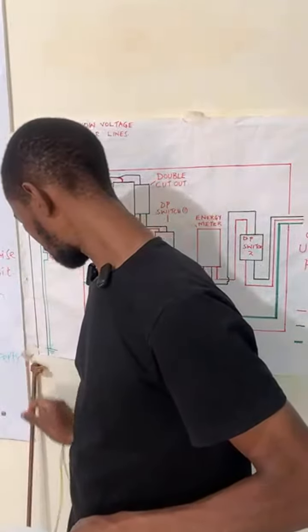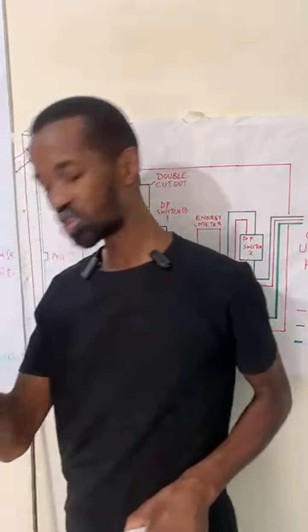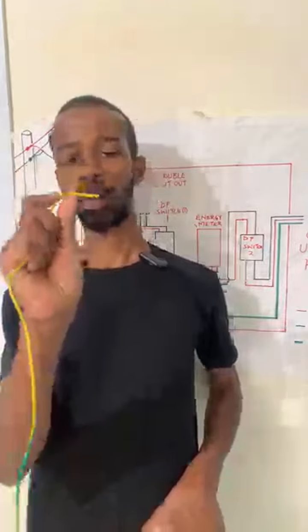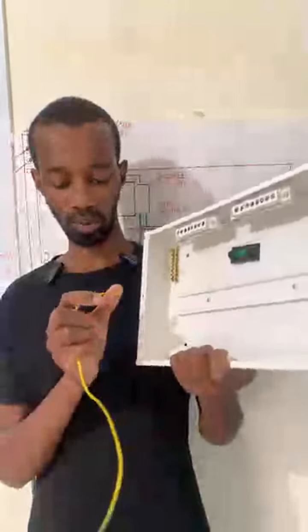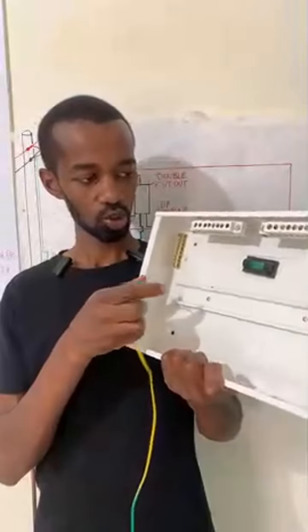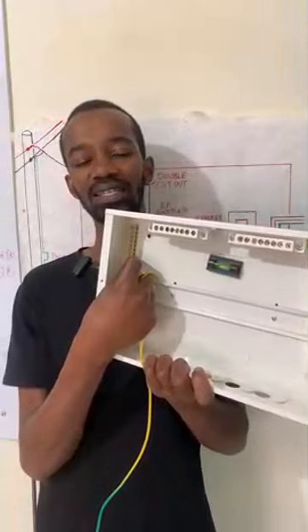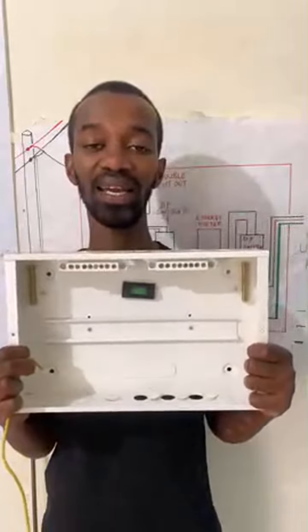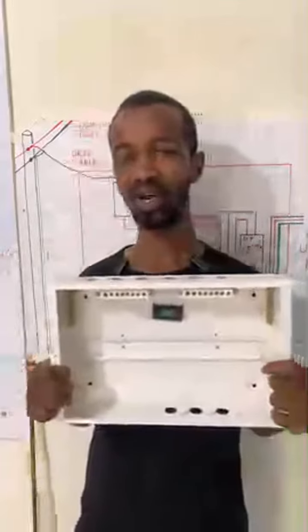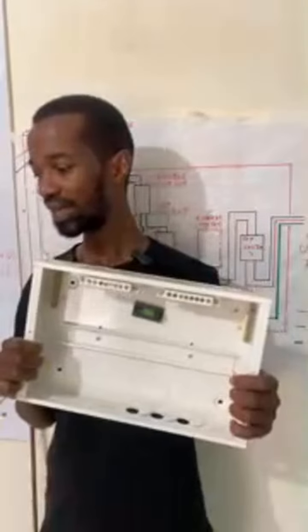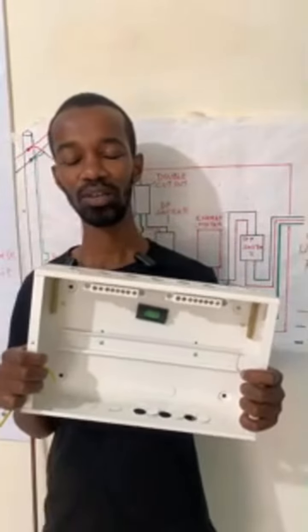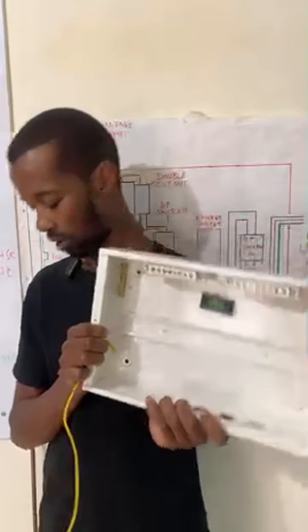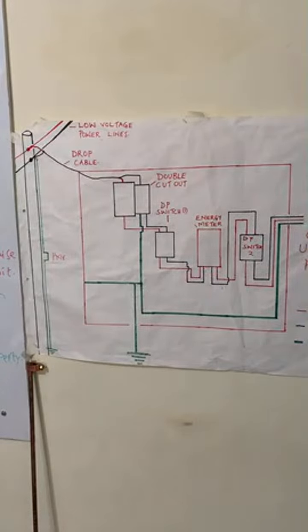All right. So top boss, if you are talking about this earth wire here, you must ensure that you strip it to expose the copper wires, so that you can even backfold it, so that when you connect at this point here, we have a great surface area, making that connection mechanically and electrically sound. What do I mean by mechanically sound? I mean that it is tight, it cannot easily get off, and also that connection is electrically sound, meaning that it is able to perform its purpose of conducting the excessive charges all the way to the meter box and down to, not the consumer unit, down to the earthing connection.